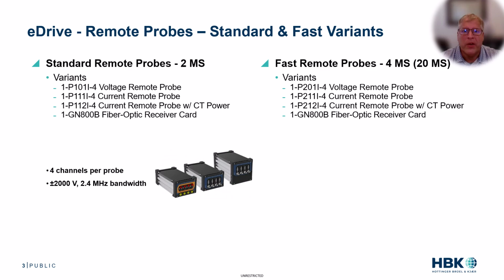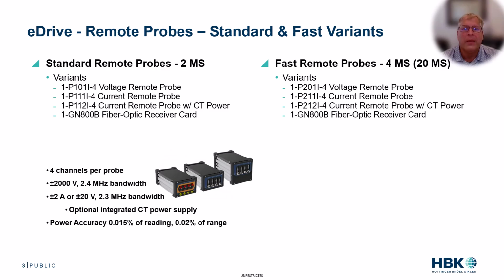Now, the voltage probe can measure up to plus minus 2,000 volts directly with a bandwidth of 2.4 megahertz, and the current probe can measure up to plus minus 2 amps from a CT using built-in high-precision burden resistors, or you can even measure up to plus minus 20 volts from a current clamp with a bandwidth of 2.3 megahertz. And there's even a current remote probe variant that includes an integrated CT power supply, further minimizing copper cabling. Now, power accuracy is an impressive 0.015% of reading and 0.02% of range.